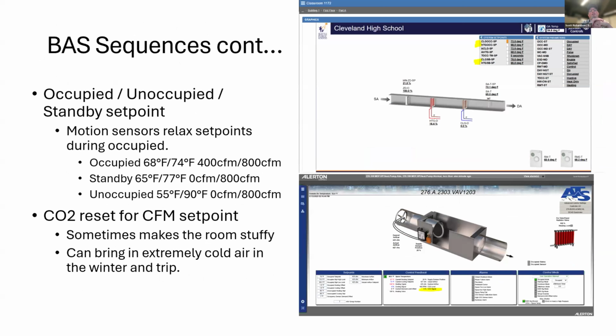So some sequences continued. We fine tune those set points. We have occupied, unoccupied, standby set points. It gets confusing for the operators because they're like, why do we have so many set points? But if you just break it out into those three conditions, you've got your occupied heating and cooling, your unoccupied heating and cooling, and then of course we integrate the motion sensors from the lighting system. And if we don't see any activity in that room, we will relax the occupied set points by 3 degrees in this example. And then you can monitor CO2, and then you can adjust how much air you're pumping into that space based on the CO2 needs. CO2 could also be used for occupancy in addition to binary PIR occupancy sensors.